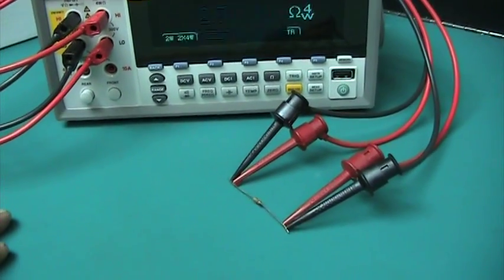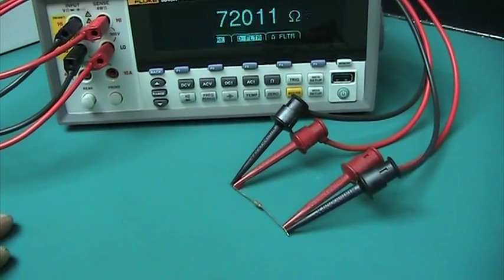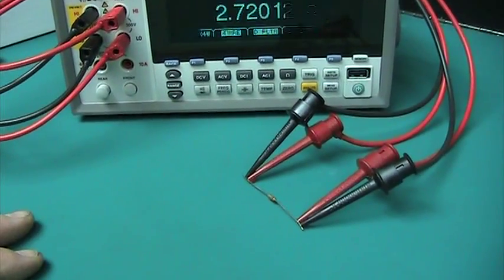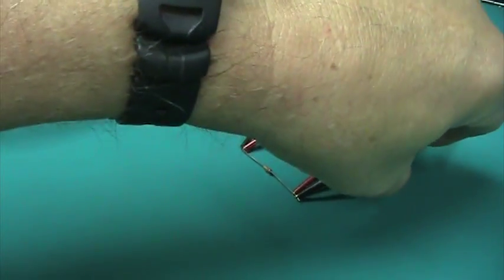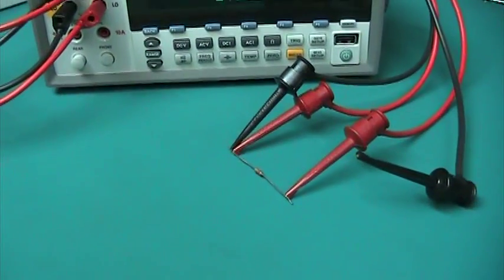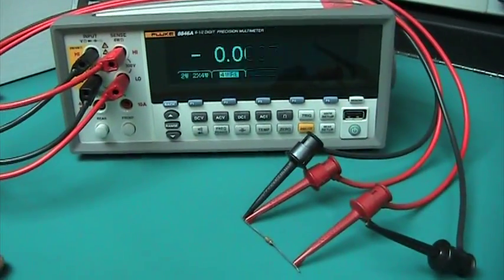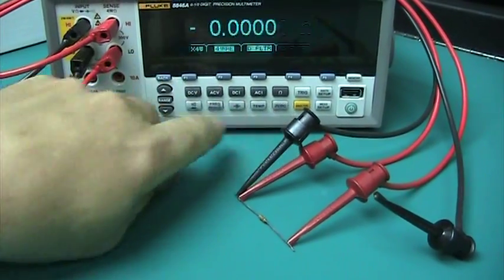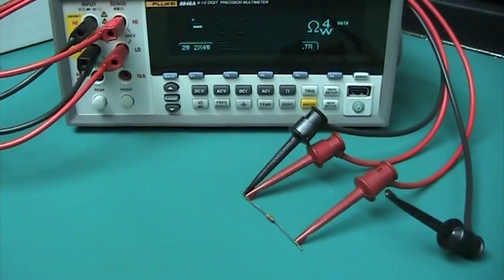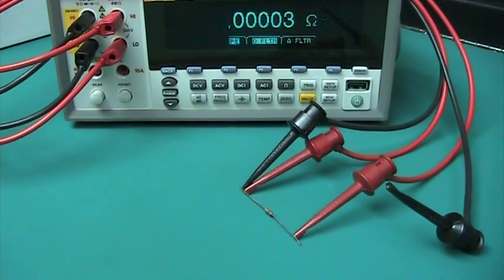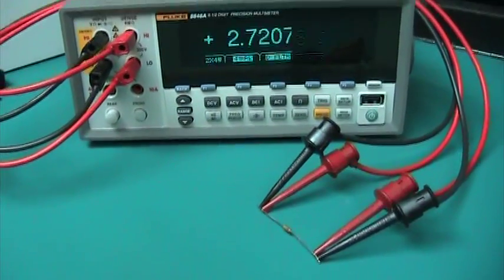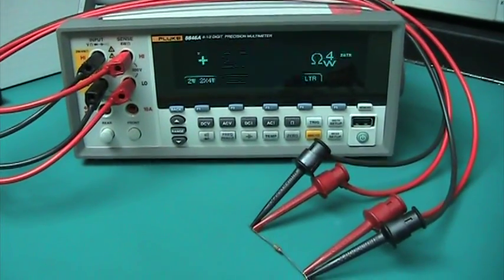How can we use a meter that doesn't have offset compensated ohms to do the same thing? We can do just what we saw here - we disconnect the current, but in this case now we go and we zero the meter out. So we've just zeroed out the thermal EMFs that are there, and now we can go ahead and connect, and now we see what the actual reading is without the thermal EMFs.